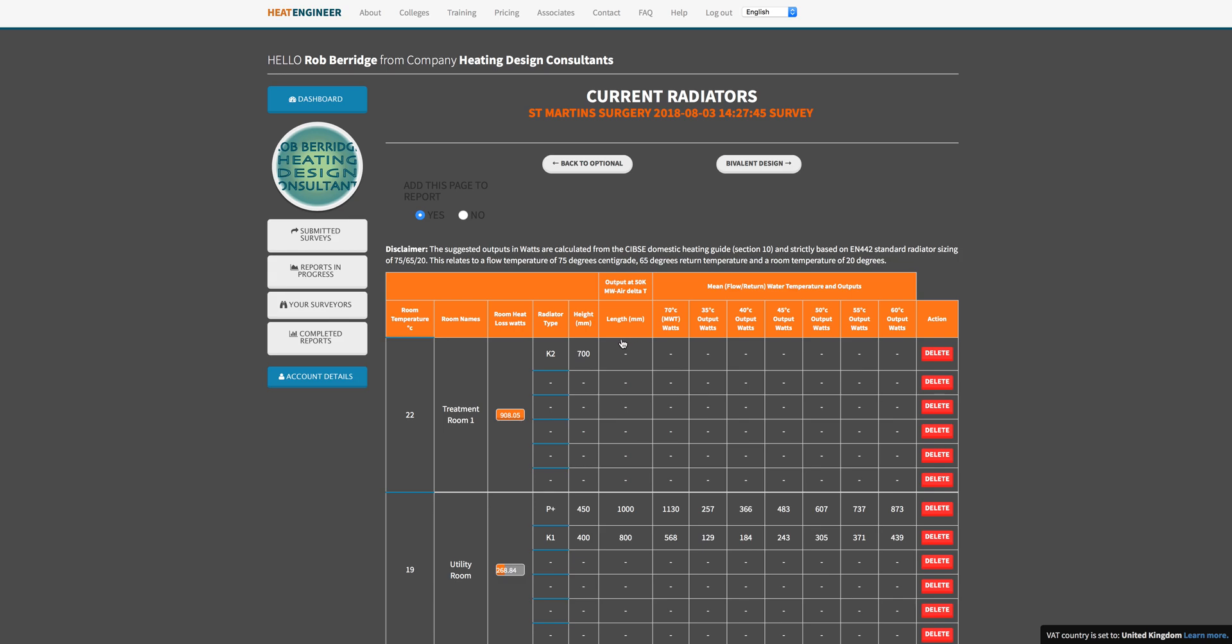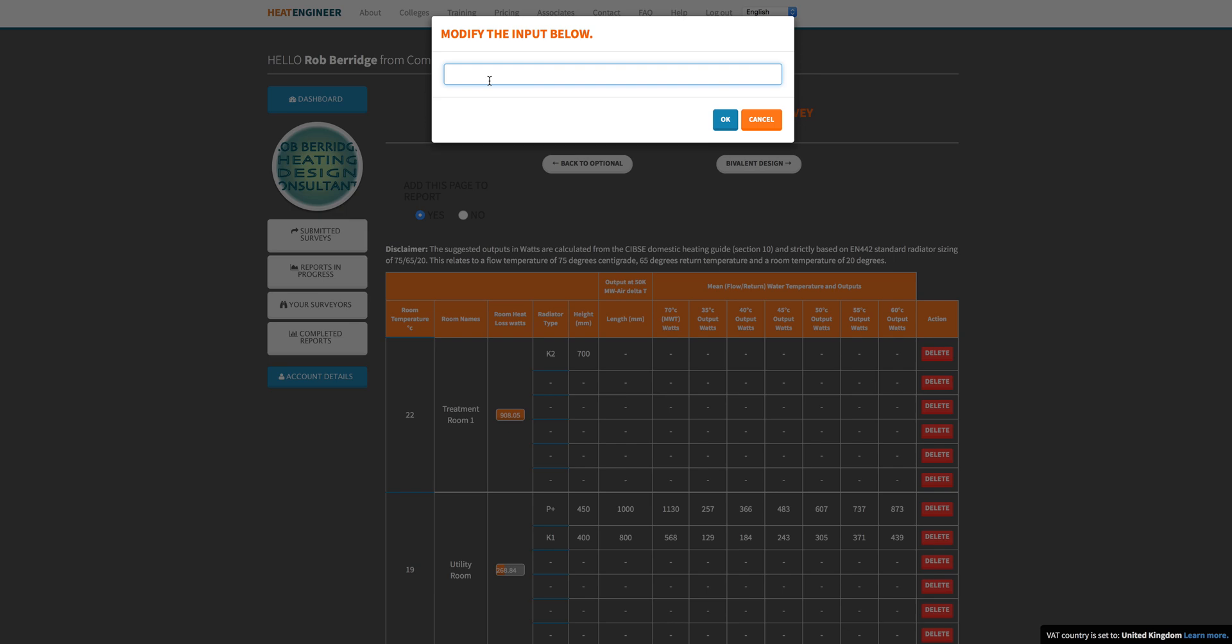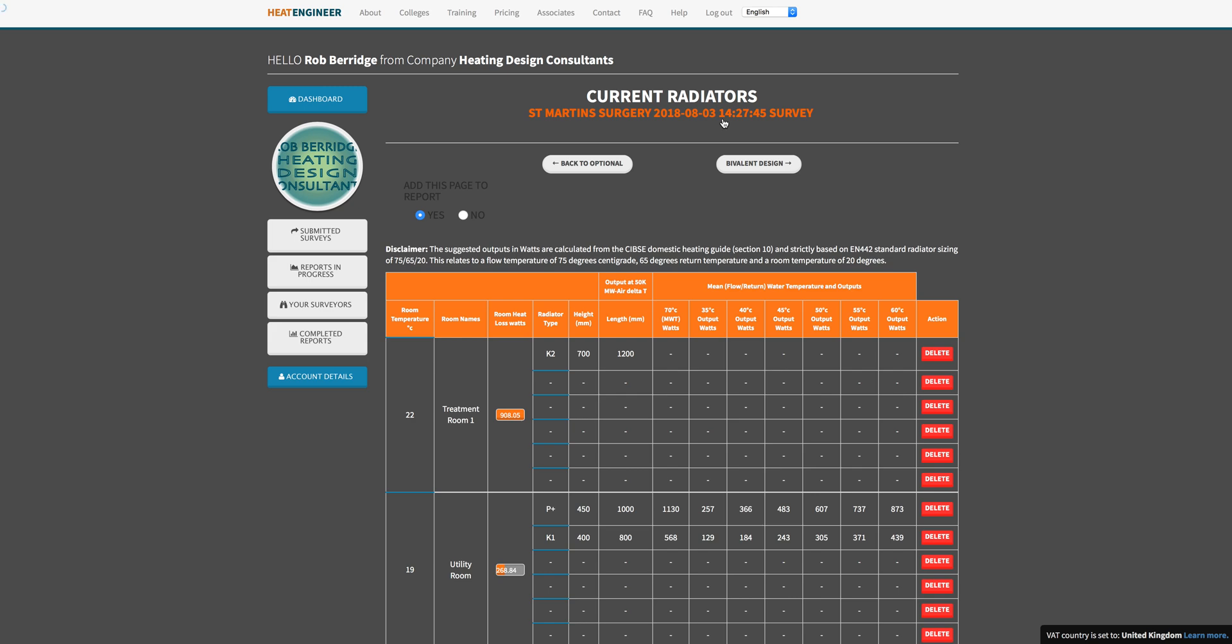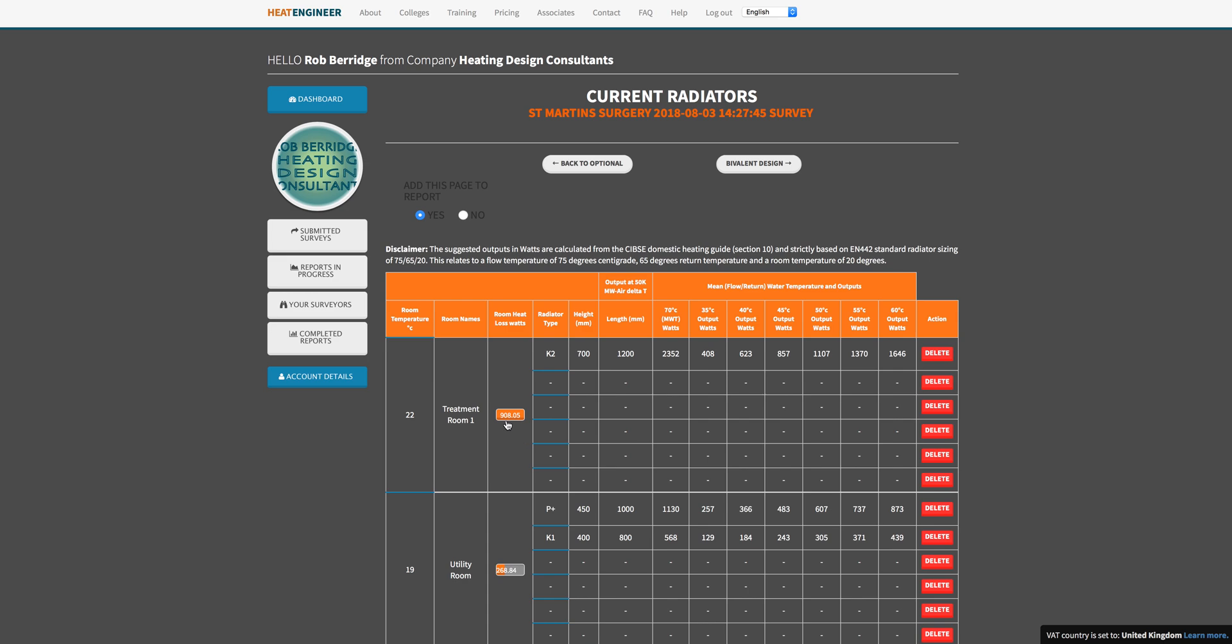Type that into the software, you can see now it just takes a bit of time and it calculates out exactly what we want. Now we can see that at different flow temperatures, these are the outputs in watts that we are going to get. Now you have to make yourself an engineering decision on what you're going to do in that scenario. To my mind, the only thing that you can do to cover yourself is to run that flow temperature at 50 degrees, or mean water temperature at 50 degrees, which is going to give you that heat loss that you require.